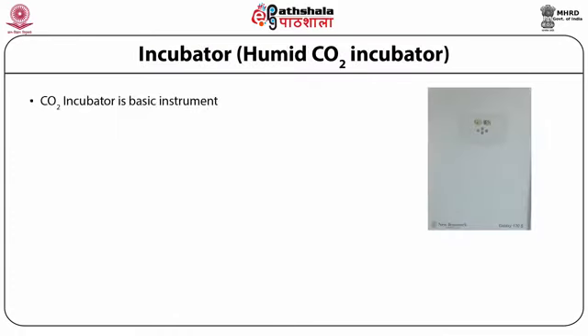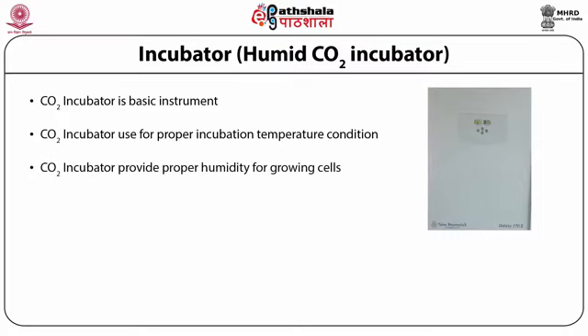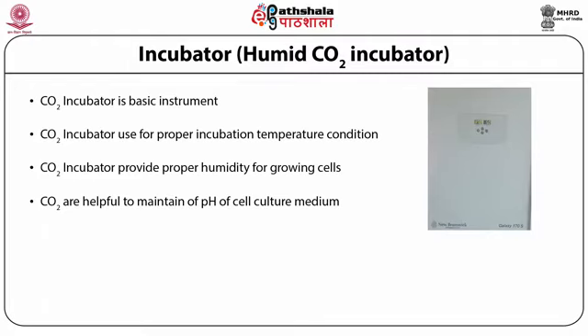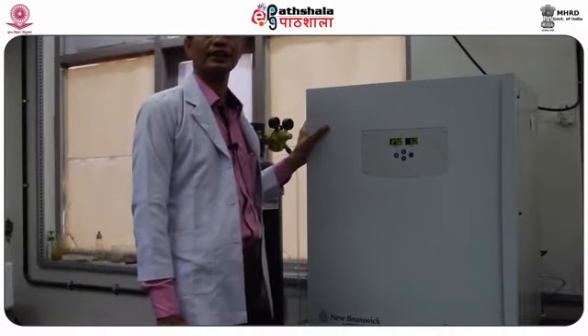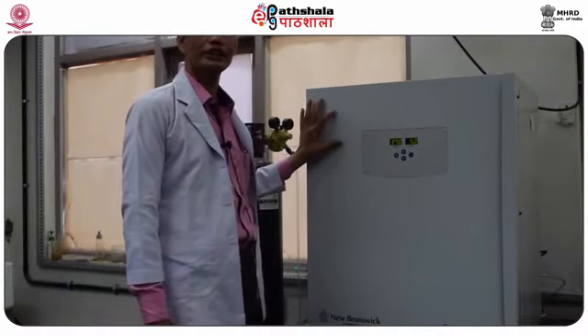The CO2 incubator provides proper humidity for growing cells and also maintains the pH of the cell culture medium, because CO2 diffuses into the medium and acts as a buffer to prevent pH changes. This is one of the basic pieces of equipment required for animal cell culture technology, known as the CO2 incubator, and it performs three functions: incubation of cells, provision of 5% carbon dioxide to maintain pH, and provision of humidity as per cell requirements.